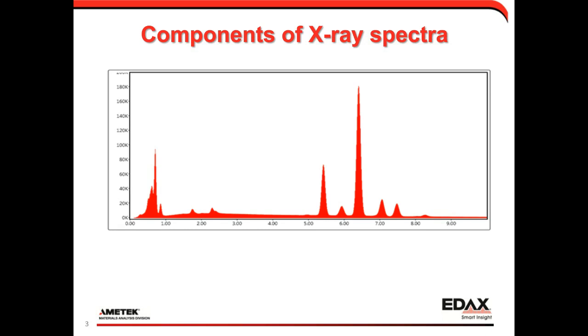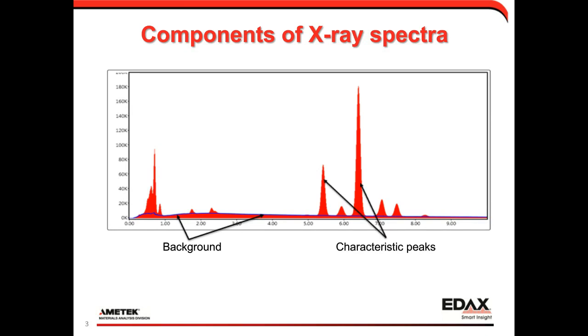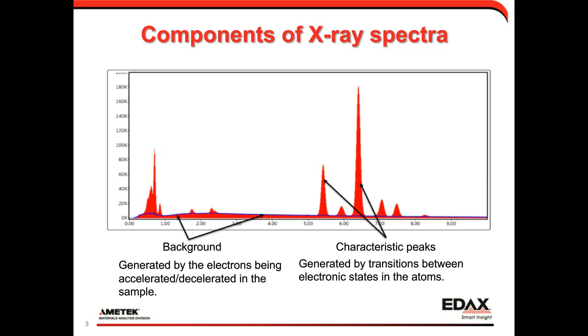An x-ray spectrum has two primary components: the background and the characteristic peaks. The background comes from electrons being accelerated or decelerated inside the sample — a continuum emission of radiation. The characteristic peaks are generated by transitions between electronic states in atoms. The characteristic peaks are what we use to determine what and how much is in the sample, while the background is sometimes considered an annoyance, but as we'll show, there's useful information hidden in it as well.